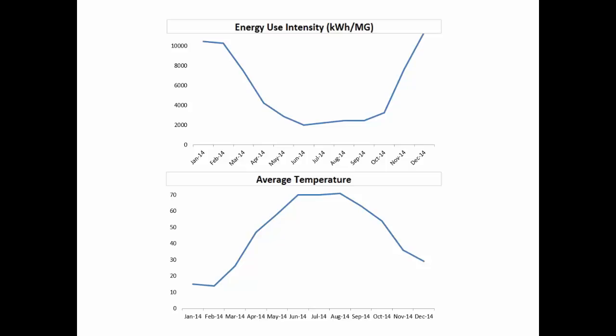So they wanted to evaluate alternate fuel sources, to see about going back to propane. They also had natural gas on the street right outside of their plant, so they had several different options. They were also considering looking at solar for heating. So they are evaluating the alternate fuel sources to heat the plant and then determining what's most cost effective, because it seems that electric is probably not the most cost efficient way to heat that water plant. So everything else in a brand new plant was pretty energy efficient outside of the heaters.